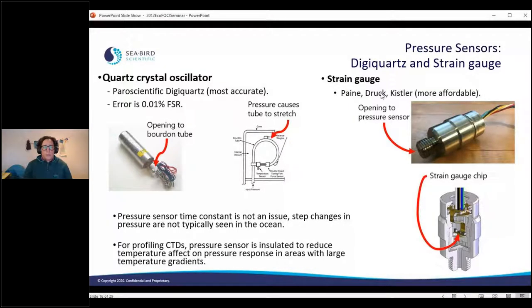One thing I really like talking about is that we do our own calibrations of strain gauge pressure sensors at Seabird, but we're not able to do that for the Paroscientific ones. The reason is because of the extremely high accuracy involved and the standards required. Paroscientific is another company out in Bellevue, and they actually have a gravitational map around their entire factory to achieve that level of pressure sensor accuracy. So it's a totally different ball game depending on the kind of pressure sensor.